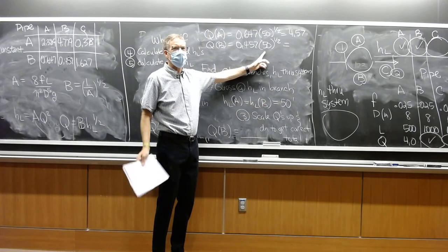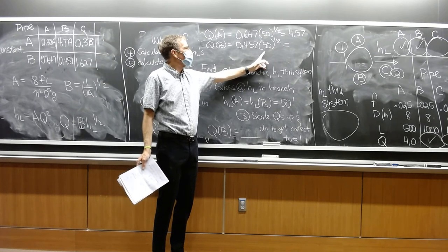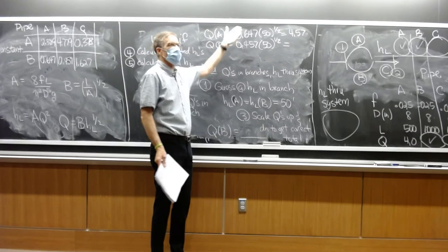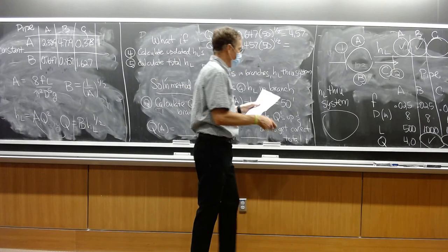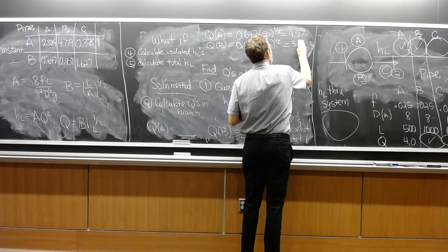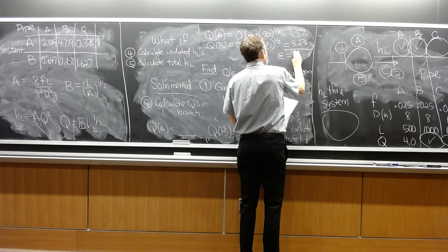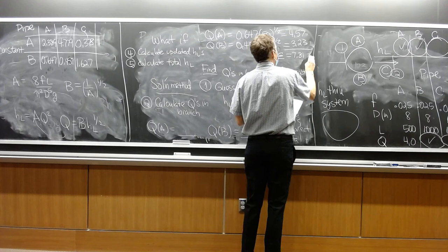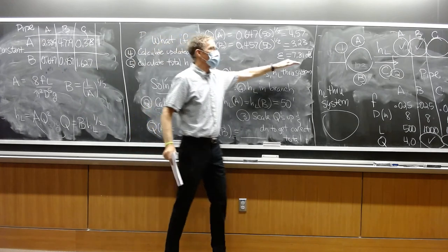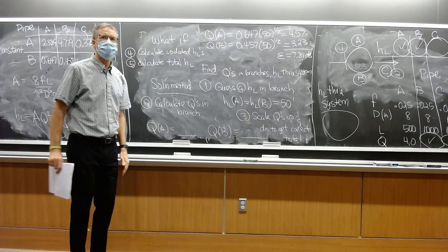And we could guess anything. You could guess 1, 100, 1,000, whatever you'd like. It will give you a distribution of flows that you can use regardless of what the total is. This one gives me that, and the total is, with 50 feet, I get a total flow of 7.81.